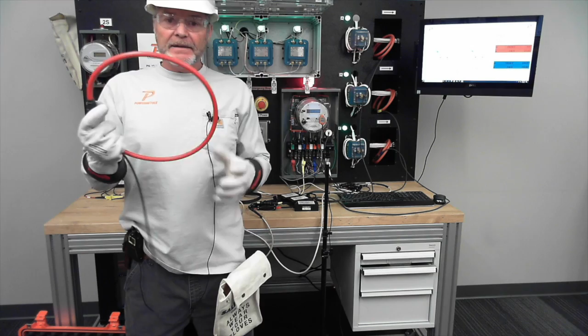Then last but not least are, of course, the flexes. I did want to mention that you have to use one of these if you have a situation where they're running 2 conductors through the same CT. So if you're running 2 conductors through the same CT, you're going to have to figure 8.